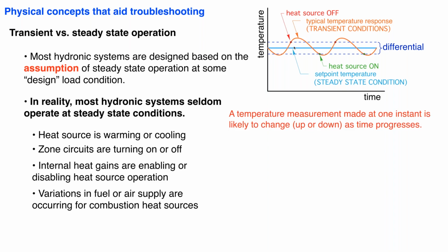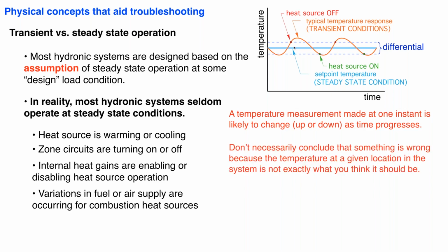So from a troubleshooting standpoint, a temperature measurement made at one moment is likely to change up or down. So if you took a reading on a meter and said, oh, the temperature is 170 degrees and the controller on the boiler is set for 180, something must be wrong. No, maybe if you wait another couple minutes, the temperature might even go above 180. So don't necessarily conclude that something is wrong because a measurement you've taken at some instant of time at some location in the system is not exactly what you think it should be.